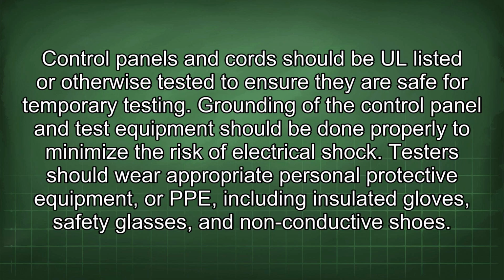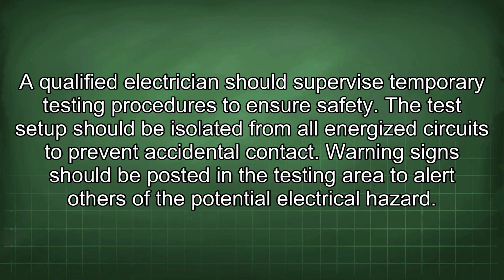Control panels and cords should be UL listed or otherwise tested to ensure they are safe for temporary testing. Grounding of the control panel and test equipment should be done properly to minimize the risk of electrical shock. Testers should wear appropriate personal protective equipment, or PPE, including insulated gloves, safety glasses, and non-conductive shoes. A qualified electrician should supervise temporary testing procedures to ensure safety.